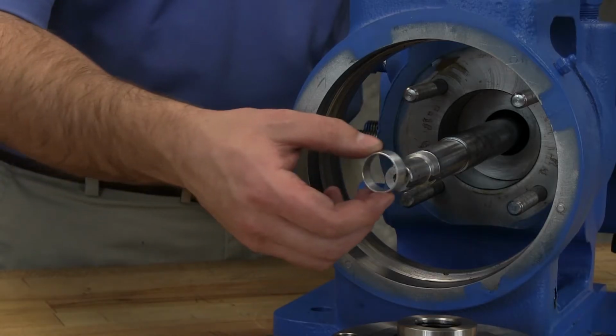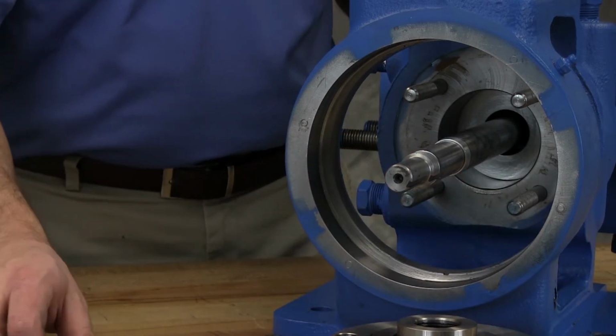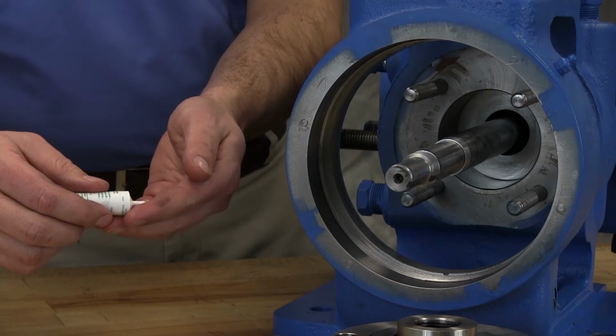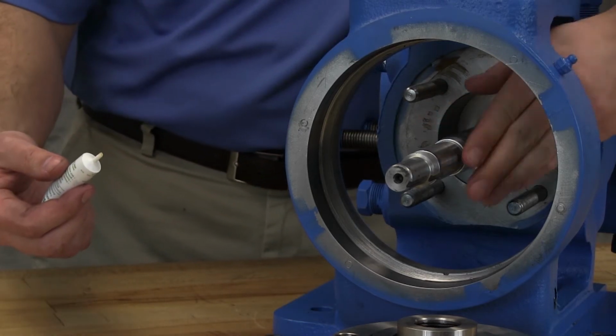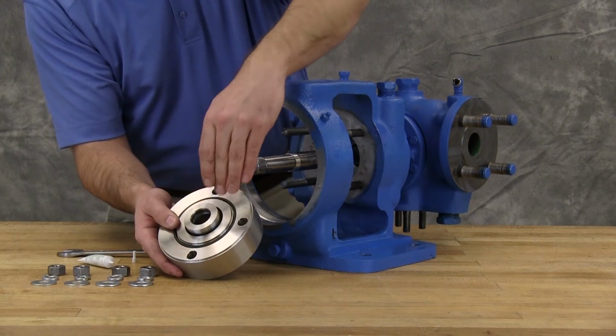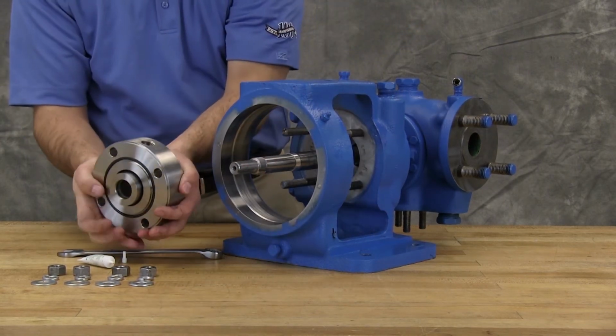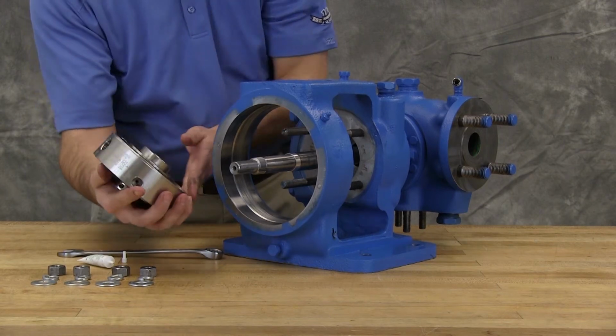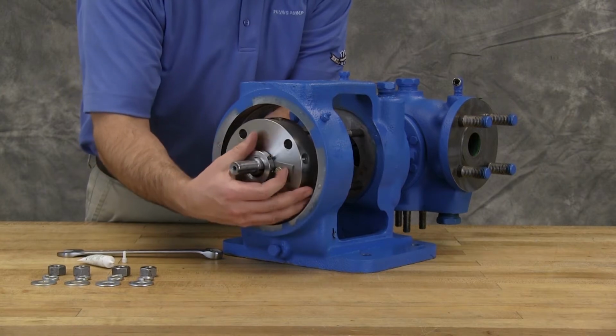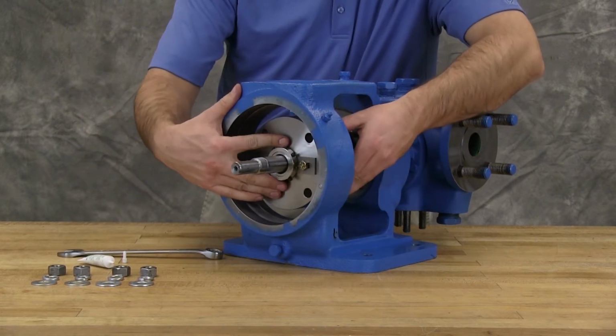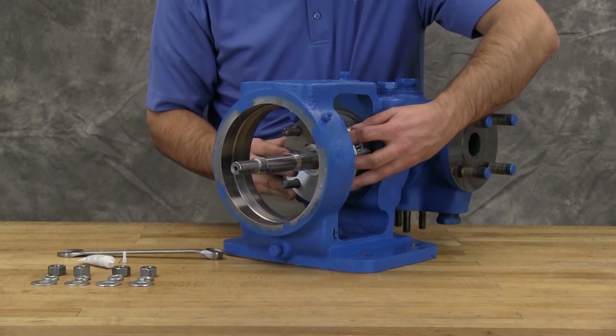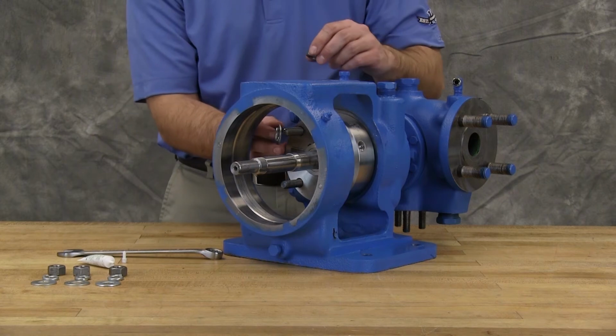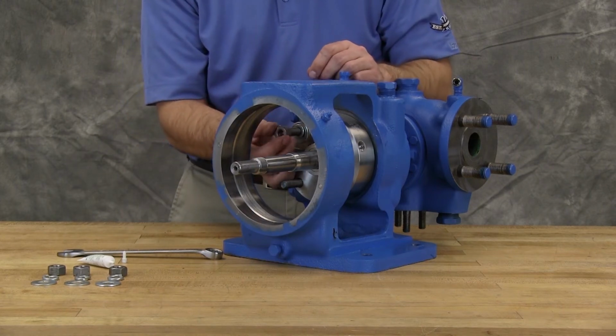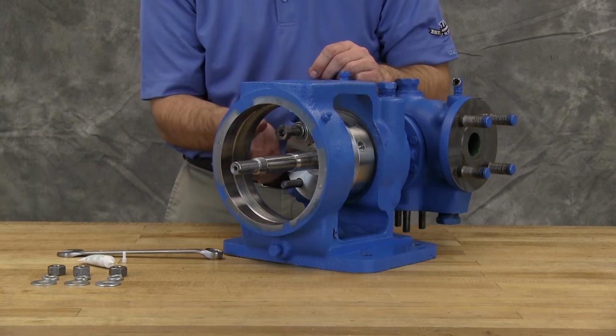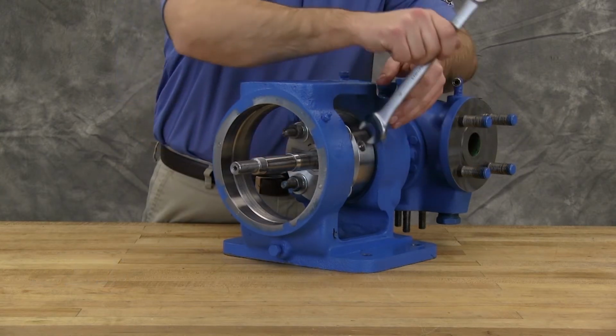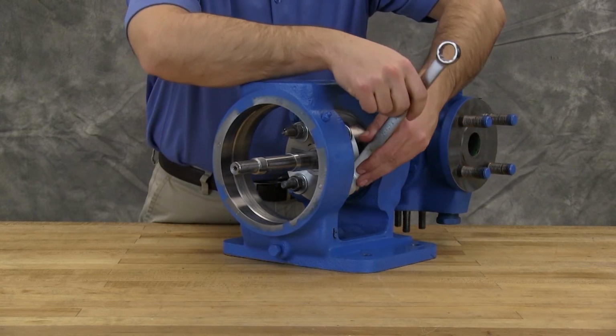Install the tapered installation sleeve on the shaft. Make sure the shaft is free of burrs that could damage the O-rings of the seal. Coat the rotor shaft, tapered installation sleeve, and the inside of the rotor member of the seal with a generous amount of light oil. Install the seal onto the shaft, making sure it is oriented with the flush port at the 12 o'clock position. Secure the gland onto the bracket face using the proper hardware. Tighten only enough to contain leakage and not to distort the seal gland.